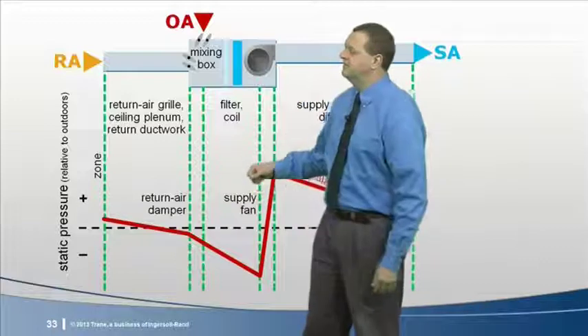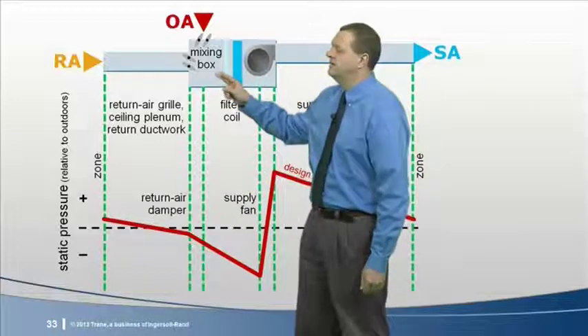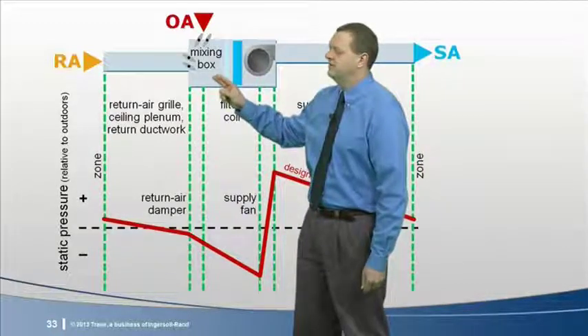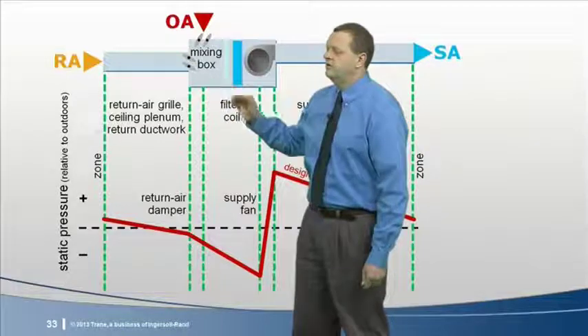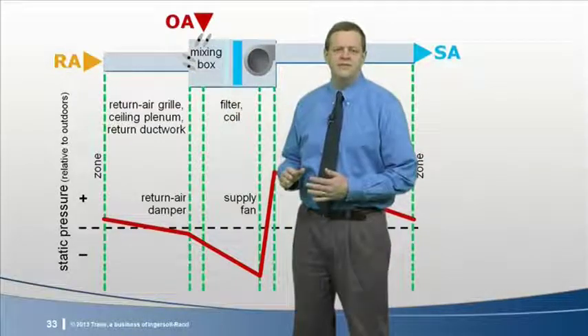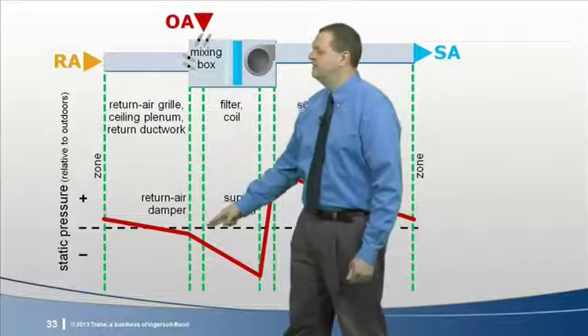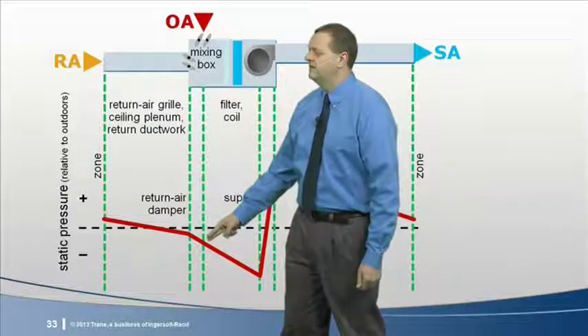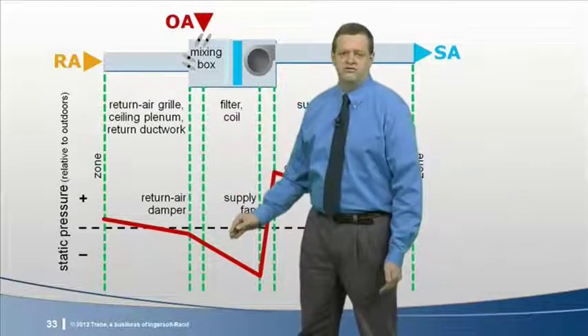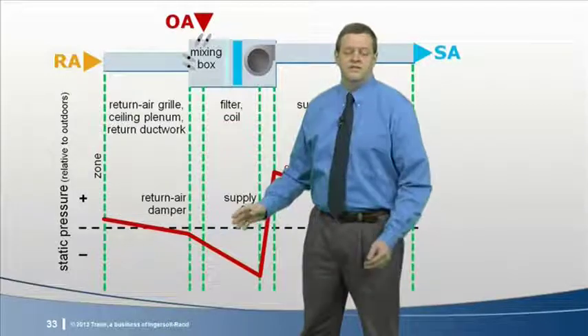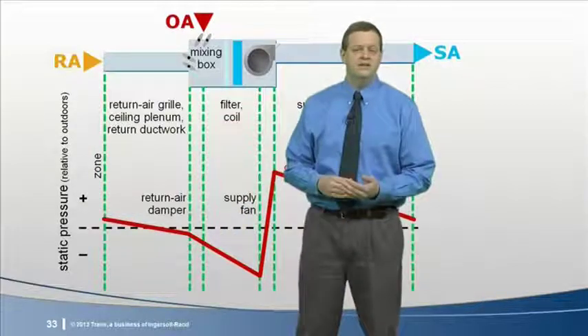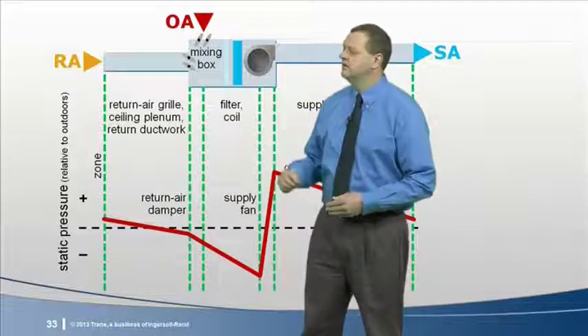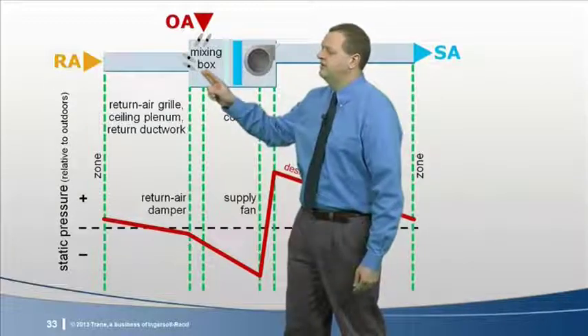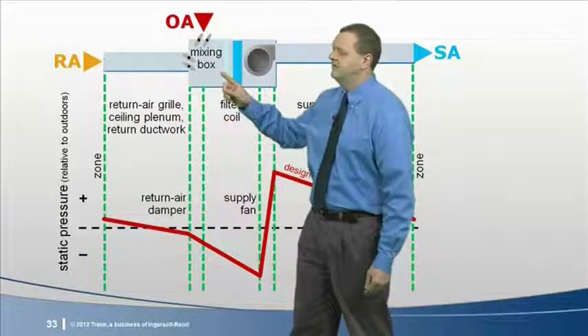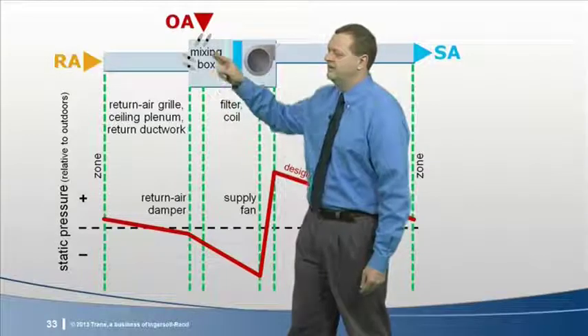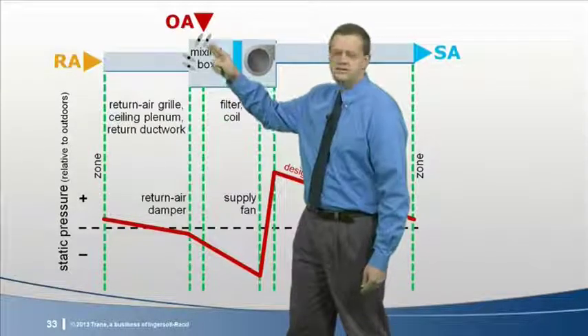For this particular system, this mixing box is where outdoor air mixes with the recirculated air. Due to the pressure drop through the return air path, the static pressure in this mixing box is negative. That is, it's lower than the pressure outside the building. This causes outdoor air to be drawn into this mixing box. The return air damper is adjusted so that the pressure in this mixing box is low enough to ensure that the desired CFM of outdoor air enters through this outdoor air damper.